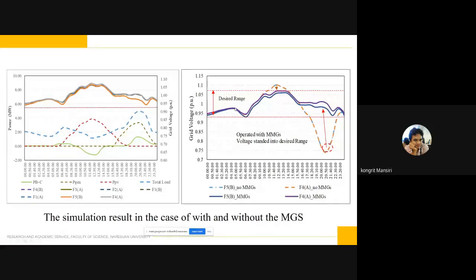Comparing with and without the microgrid system in this area, you can see here the voltage is more stable. The dotted line is without the microgrid system. During the daytime, the voltage is sometimes 1.1 pu. So when they have the battery, the grid voltage decreases into the desired or acceptable range. In the evening time, the voltage also increases to the acceptable range, because the batteries can supply the load, and they also have a switch to disconnect some feeders if the battery cannot supply.